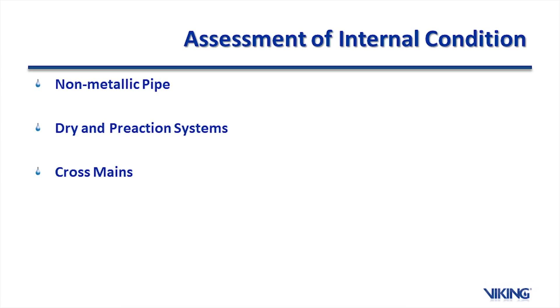Now, in certain cases, you're not going to need to do that for non-metallic pipe because we're not really worried about corrosion in non-metallic. You do need to do it for dry and pre-action systems. They are required to do so, and you're going to need to do it in the cross mains as well.